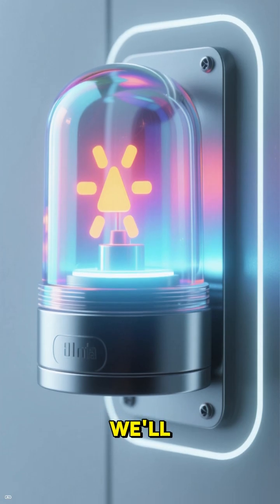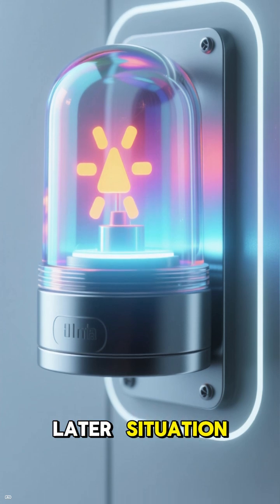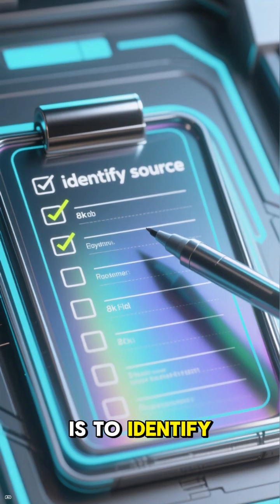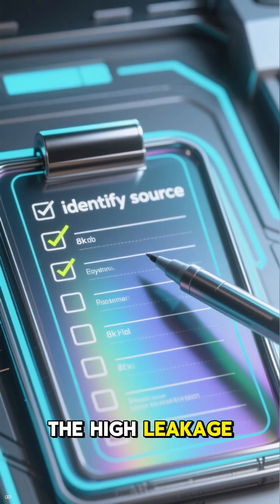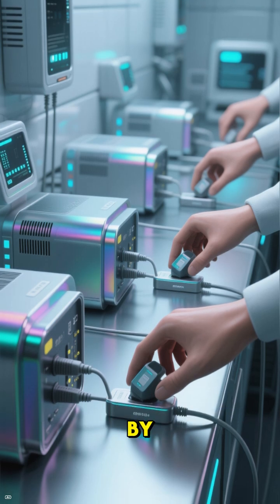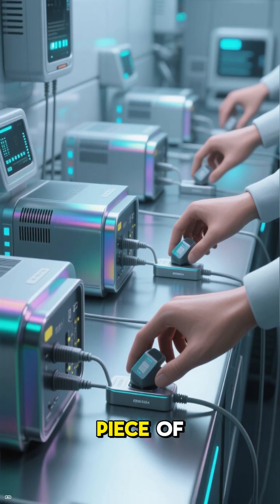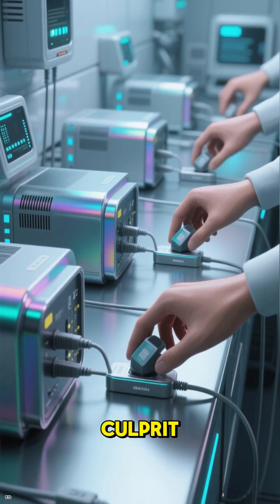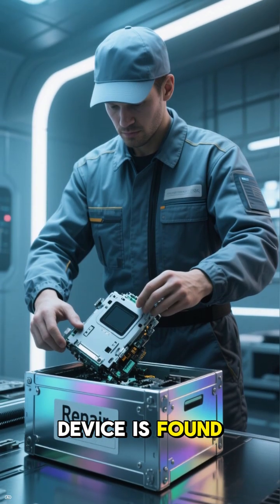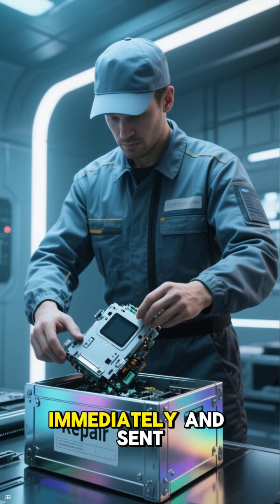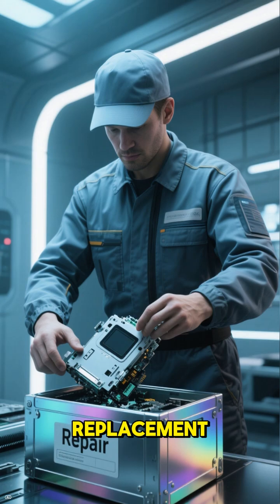This isn't a "we'll get to it later" situation. The first step is to identify the source of the high leakage. You start by unplugging devices one by one and retesting to see which piece of equipment is the culprit. Once the faulty device is found, it must be removed from service immediately and sent for repair or replacement.